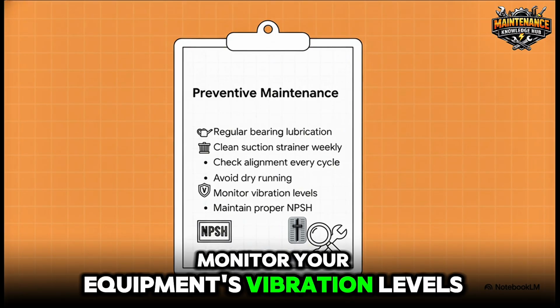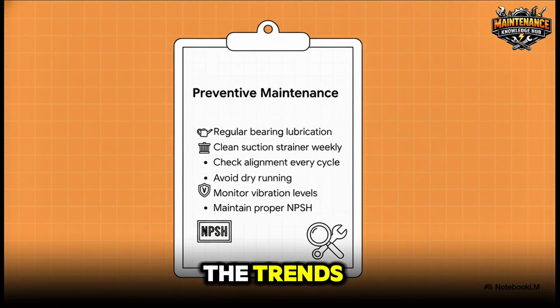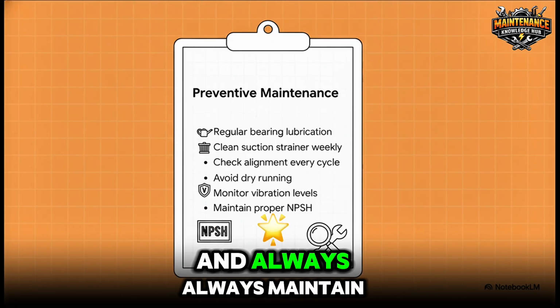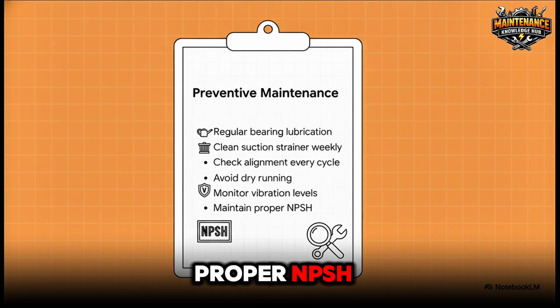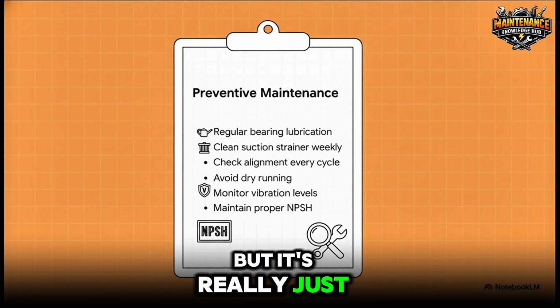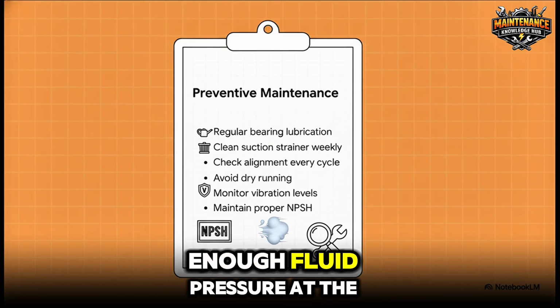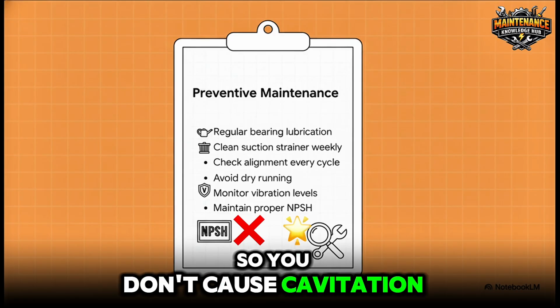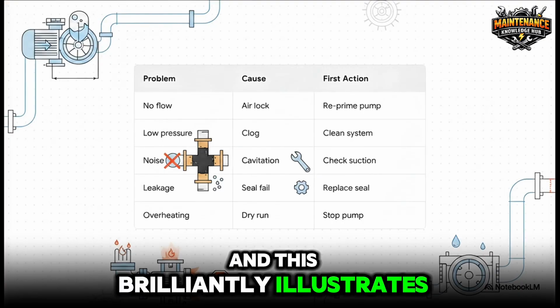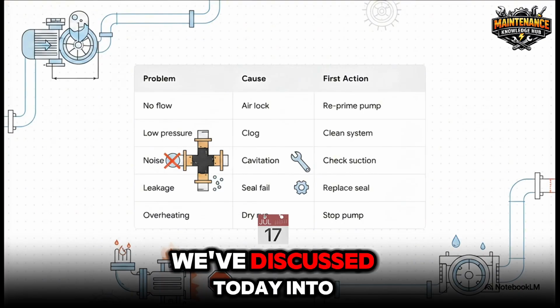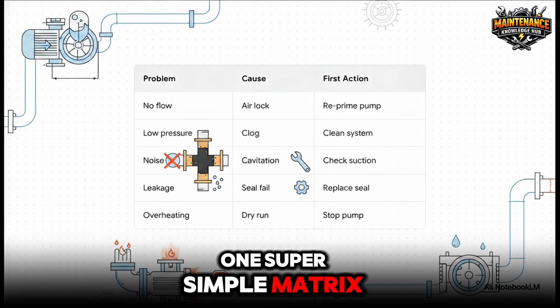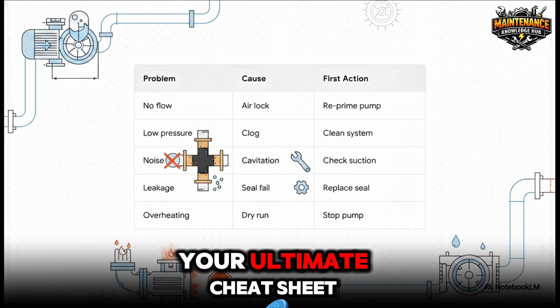Monitor your equipment's vibration levels over time so you can actually spot the trends before they turn into full-blown failures. And always maintain proper NPSH, which stands for net positive suction head. I know it sounds super technical, but it's really just a fancy way of saying make sure there's always enough fluid pressure at the pump inlet so you don't cause cavitation. And this brilliantly illustrates how we can pull everything we've discussed today into one super simple matrix. Think of this as your ultimate cheat sheet.